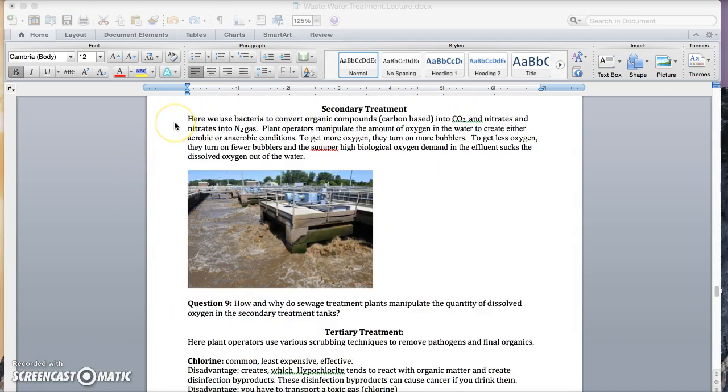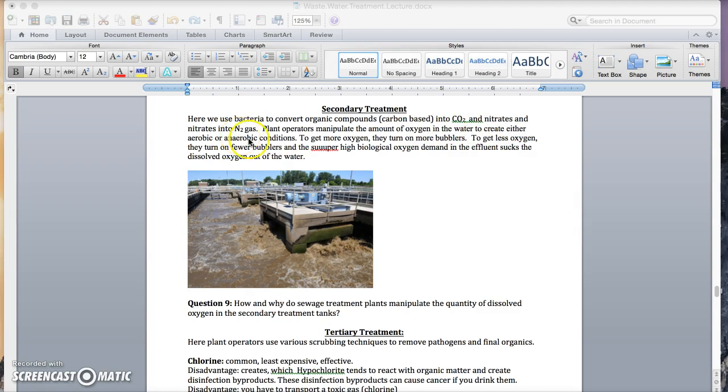In secondary treatment, we use bacteria to convert organic compounds, which are carbon based, into CO2 and nitrates and nitrites into nitrogen gas. Here, plant operators manipulate the amount of dissolved oxygen to figure out whether they're going to have aerobic or anaerobic bacteria, which will then move the water through the different steps of the nitrogen cycle. Pause here for question nine.